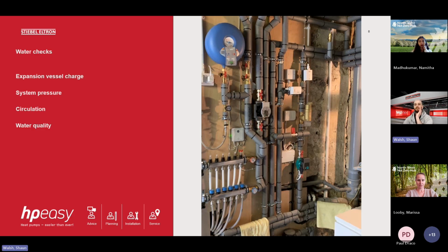If system pressure, expansion vessels, or flow rate, if none of those things are right, the heat pump will generally run, and again, it will run inefficiently. So if you have low pressure on the heating side of the system, which is what you check on this gauge here, and it drops from the normal operating pressure of say 1.5 bar to 0.5 bar, the system pressure would drop, which would decrease the flow rate of the system. That means the heat pump can't effectively transfer the heat at the speed it would like to, and that would cause issues inside the heat pump, even though it's not the heat pump that is actually at fault. Okay. So, like I say, the heat pump will still run with poor flow, but it will just run badly. The key takeaway from that is water quality checks. Okay.